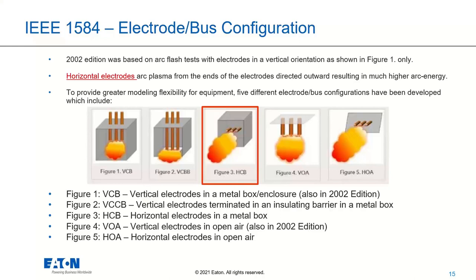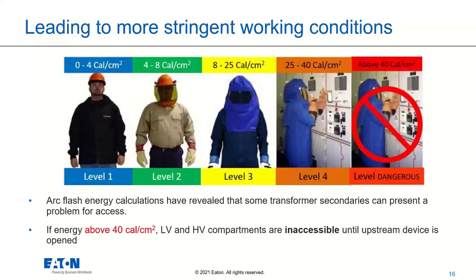So what we've seen in terms of changes from the 2002 to the 2018 edition is, in some cases, it was a pretty good representation. If you were over here on figure one, 2002 gave you a pretty good idea. It's a pretty good middle of the road. If you actually were somewhere in the open air scenario, perhaps 2002 was a little more stringent than you needed to be. This is less bad comparatively to what we had assumed. But in other cases, like this horizontal electrodes in a box, it can be far worse. We can get to nearly 190% of the value that we would have calculated with our 2002 edition. So you can imagine if I calculated in 2002 that I had, say, 22 calories per centimeter squared, I was somewhere in this level three. Yes, I had my moon suit on, but I felt I was relatively protected.